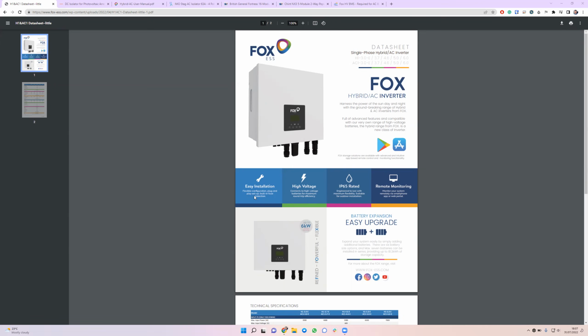So first of all, reasons for wanting to isolate the system. You may be having any work done on the electrical system of your house. You may wish to be expanding the battery capacity of your system. You may have a fault, and the first step of troubleshooting a fault for most of the error codes is actually to restart the system.